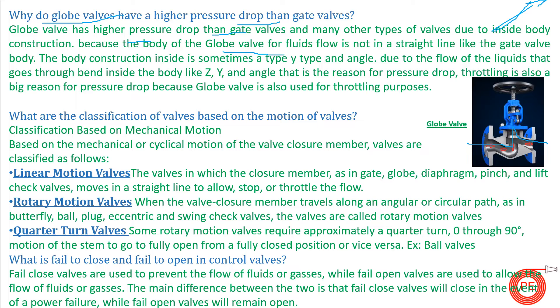Taking a Z-type globe valve as an example: fluid enters, goes upward, then changes direction again — forming a Z-shape. Because of this direction change two or three times inside the valve, there is a considerable pressure drop. In a gate valve, the flow is linear — it enters and exits in the same straight direction — so the pressure drop in a gate valve is very low compared to a globe valve.